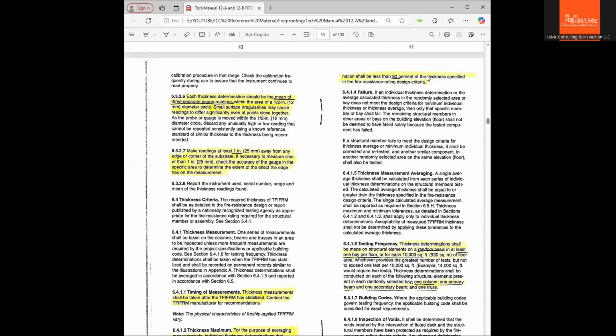So if the specified thickness to be acquired is 100, the thickness measurement should not be less than 80% of that, should not be less than 80. Let's say 100 mils, so the measurement should not be lower than 80 mils. If in a certain condition you find it has less than 80%, you should ask the applicator, the technician, to spray more on that particular area of measurement.